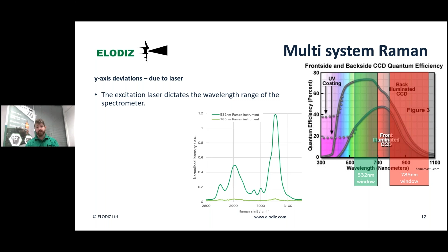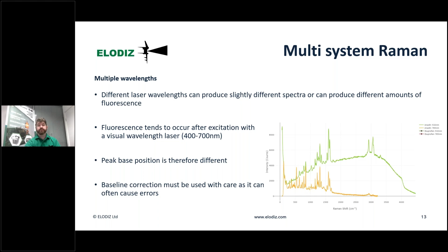The last problem, again, with multi-system Raman is the other photoluminescence effects that you're going to see in your spectrum when you're trying to perform Raman spectroscopy. As you can see, these are the analysis of the same tablet. One of them has some form of fluorescence, which is interfering with the signal and will ultimately affect the correlation score and possibly peak fitting, depending on how the peak bases that you attribute are calculated, and how the algorithms are then used to calculate peak positions, etc. So this is where using baseline corrections, etc., and peak base approximations are really important, but must be used with significant care and require a lot of knowledge to perform.